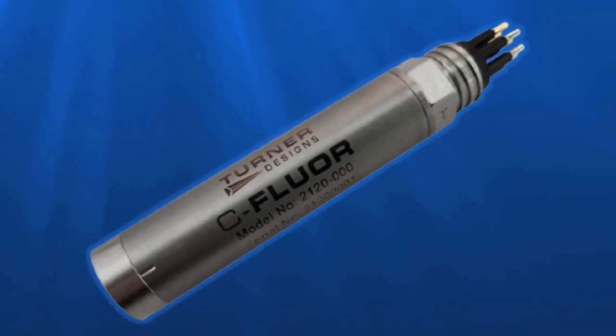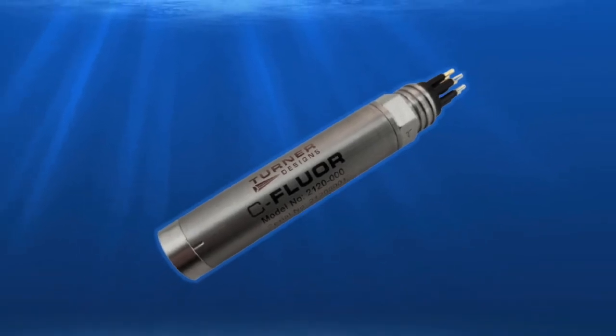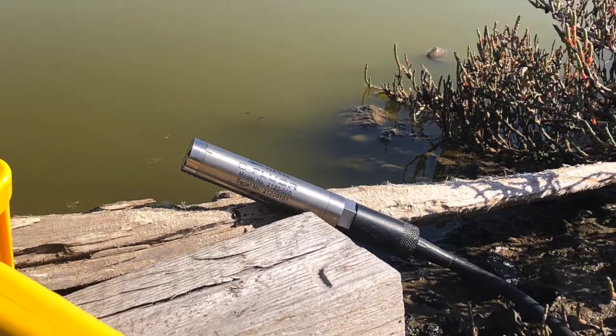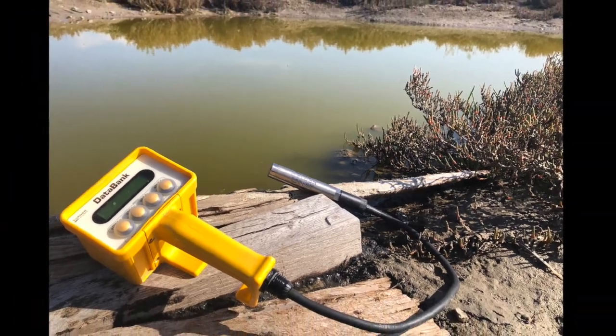C-FLUOR submersible probes are sensitive, extremely low-power, single-wavelength, in-situ fluorescence and turbidity sensors available in several optical configurations. Requiring a maximum of 12 mA current at 12 VDC input, C-FLUOR probes can be integrated and deployed for much longer intervals than previously possible with submersible probes. With a very fast response time of less than 0.6 seconds, they require even less power, outputting data soon after power is applied.